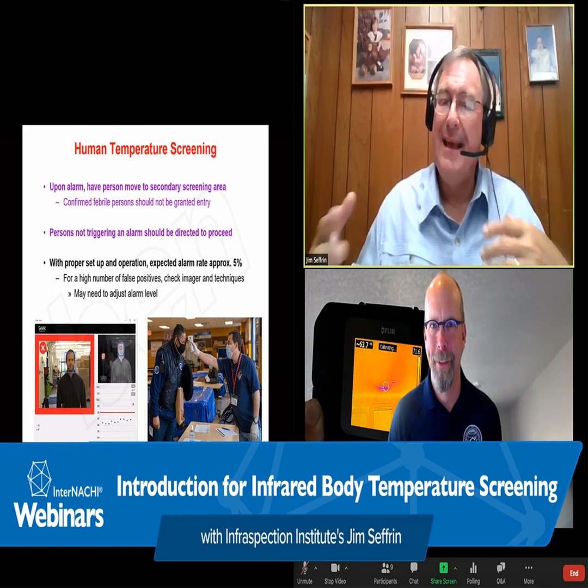When you set up your industrial grade or portable imager, you're going to set your imager inputs for atmospheric correction, such as air temperature, humidity, and distance. You'll set your imager input for lens transmission to 100%. You then select an appropriate imager measurement feature such as crosshair, isotherm, or if you're so equipped, max temperature. You connect your cables and power supplies as necessary, and secure all cables, tripods, and power supplies to avoid tripping hazards in the screening area.